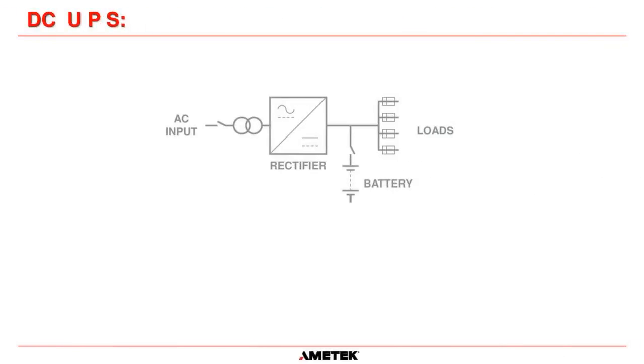So here is the most basic single line drawing for a DC system. And obviously what you can see is we have an AC input on the left-hand side here. Now, with AMETEK SCI, we only make three-phase input charger systems, but there are other manufacturers who have single-phase inputs if necessary. But for us, it's usually going to be three-phase 480 or three-phase 208 that goes into the charger.